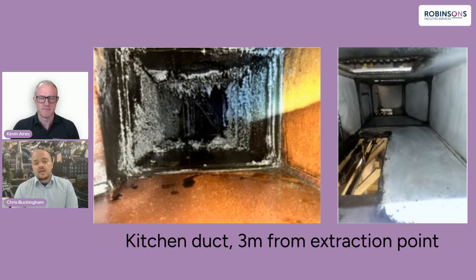Yeah, massively. This is specifically a kitchen extract system that runs on extract purpose, and like you said, it's a fire risk. As soon as that goes off, the smell of that grease and burnt-on carbon will come back through the kitchen area, and it won't be very pleasant. And if your ventilation has a loose joint or loose access door - don't forget this runs through a hotel - there's every good chance you get a whiff of that, and that's not the sort of thing we want. But yes, back to the fire risk, massively.